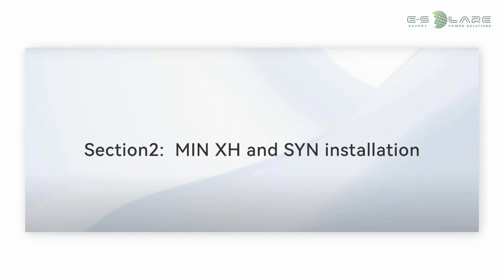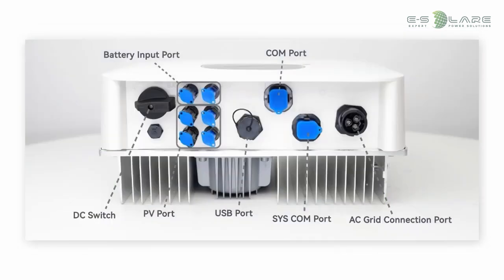The next section is how to install our MIN-XH and SYN system. If someone wants to install them outside, we recommend you at least build a shield or something else to protect the whole device. This is underneath of the inverter. There's one AC grid connection, and we're using a syscom port for communication and a USB port for the dongle for the data logger. And sometimes we also use this USB port to upgrade the whole device. And the battery terminal and two PV strings. Also there's a DC switch here.